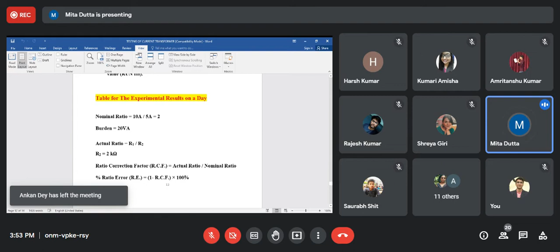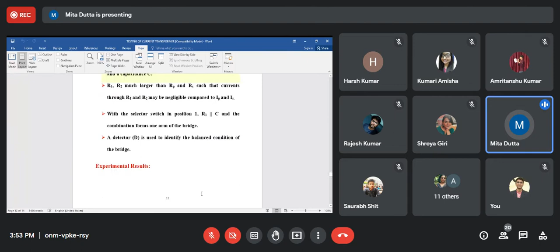But the actual ratio we have just found out from the phasor diagram from this experiment, and considering the phasor diagram of CT, it will be R1 by R2, and then the ratio correction factor, which will be the actual ratio divided by nominal ratio. Now percentage ratio error will be 1 minus RCF into 100. Therefore, it will be nominal ratio minus actual ratio divided by nominal ratio into 100. What I have written here, the ratio error. This is Kn minus R by Kn into 100.